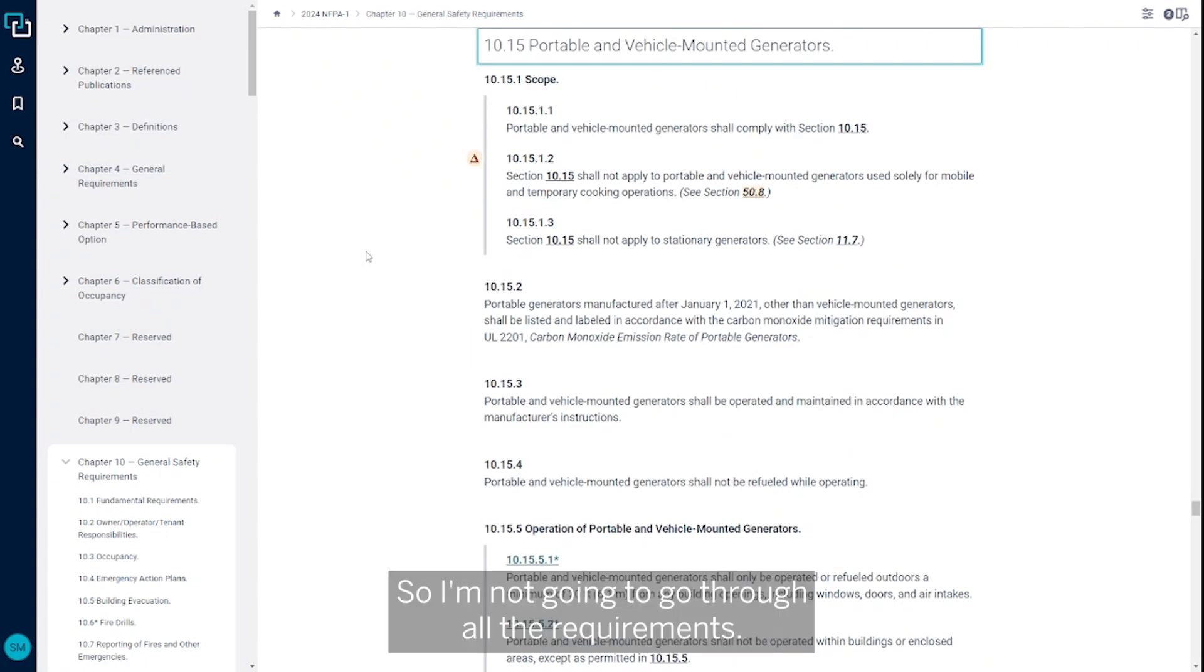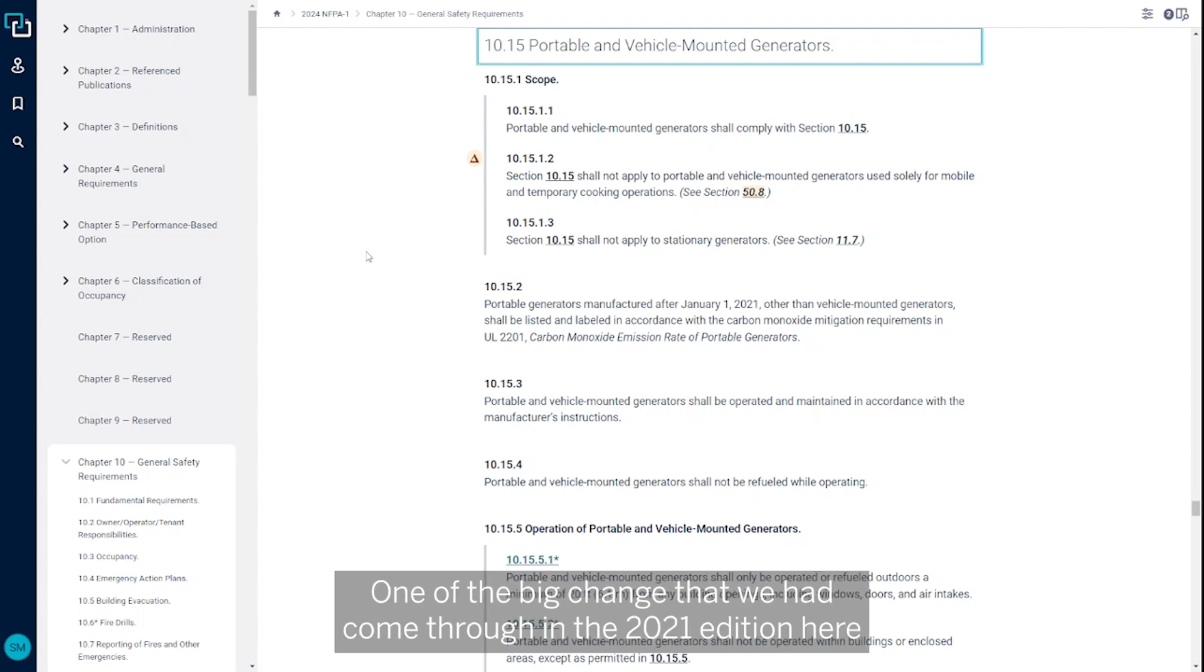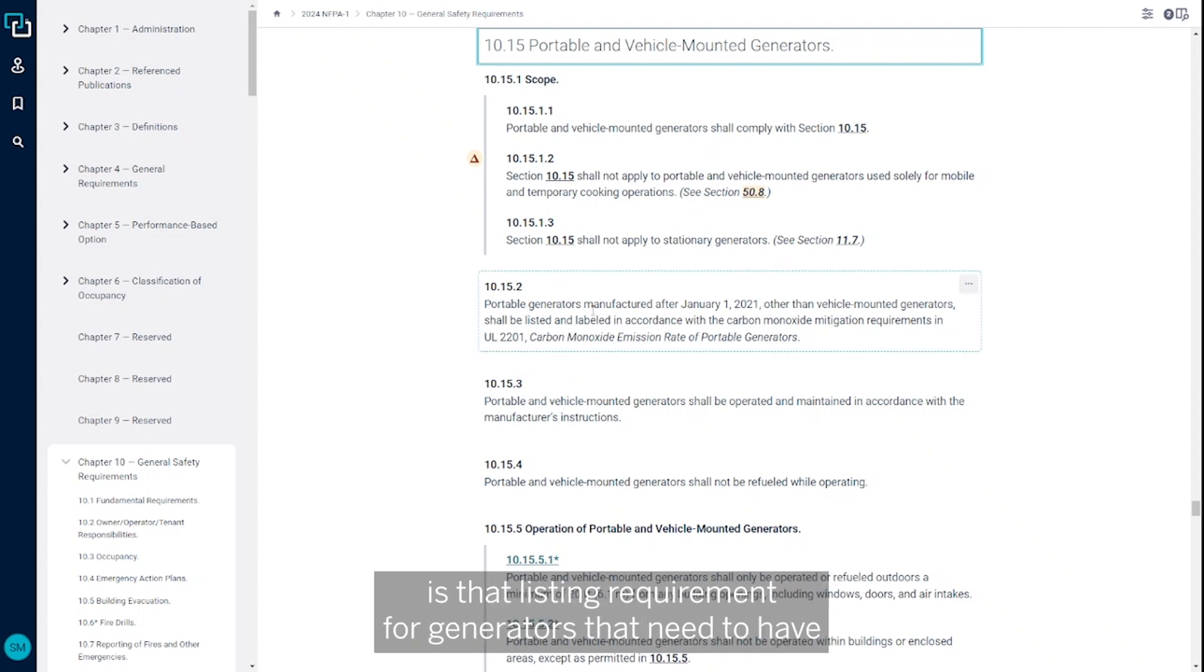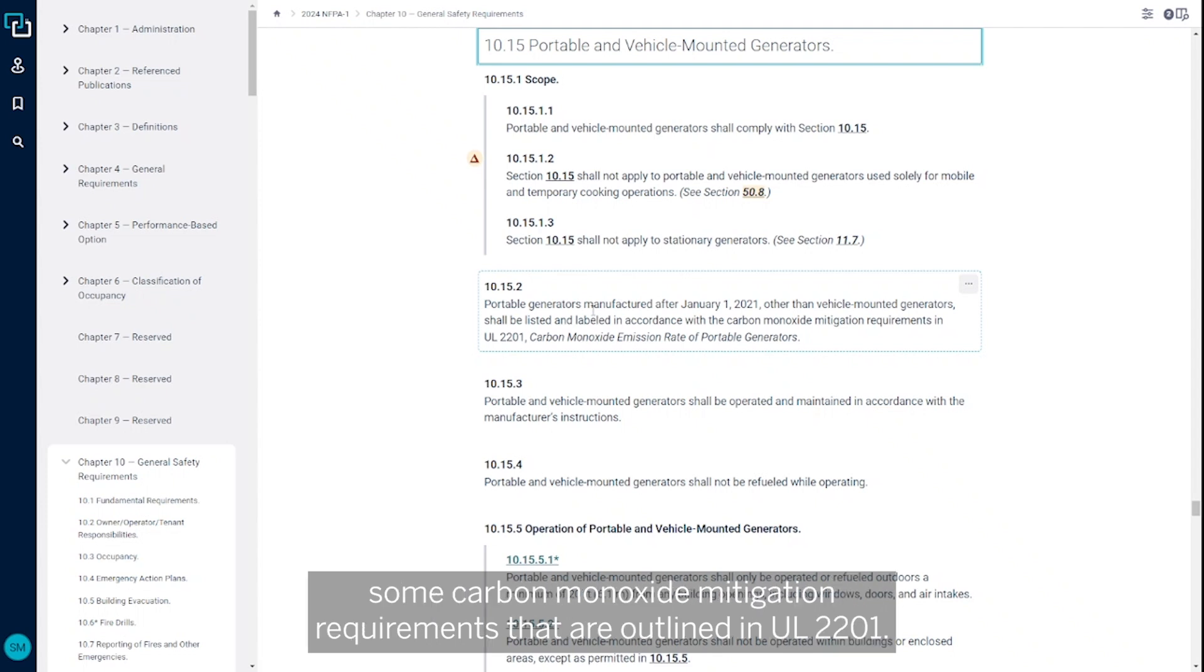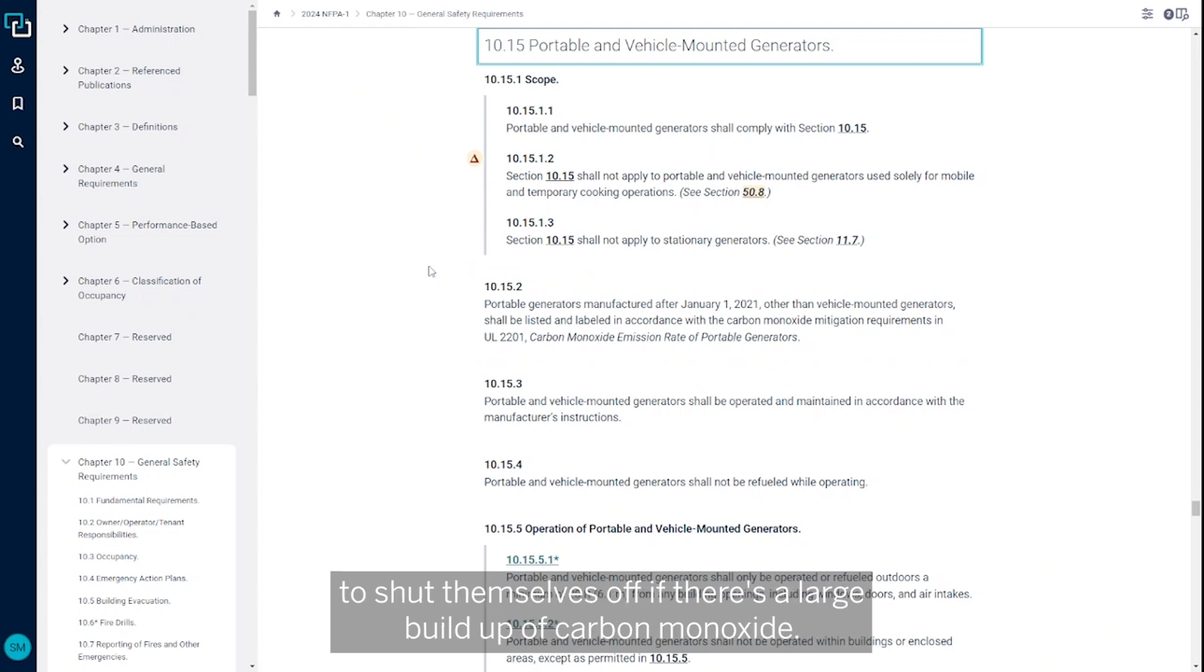I'm not going to go through all the requirements, I'm just going to highlight some of the big ones here. One of the big changes that came through in the 2021 edition is that listing requirement for generators that need to have some carbon monoxide mitigation requirements that are outlined in UL 2201. So that's something you're going to see with a lot of newer generators - the ability to shut themselves off if there's a large buildup of carbon monoxide.